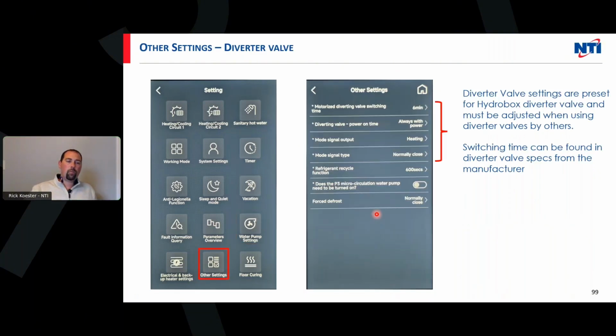Some other settings we do have if we're not using the hydro box itself and we are using somebody else's diverter valve. I'm not sure which valves you may be familiar with, but if you were going to use another valve, then we need to go in there and program the switching time of that valve. Every manufacturer has a different switching time. We have pre-programmed 6 minutes for the one that's in our machine. So basically, in between a domestic and a heating call, how long does it take to switch that over? And we're using 6 minutes. We set that this way we're not turning a circulator on before that valve is totally switched over.